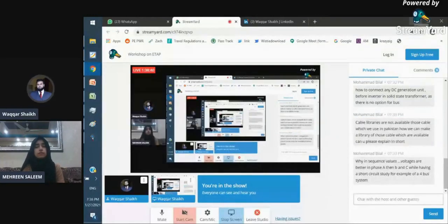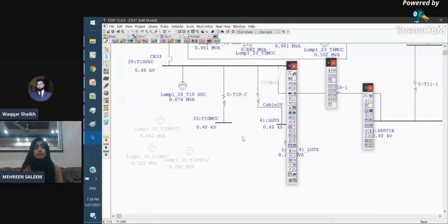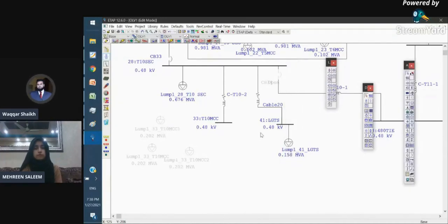Very good question, because ETAP's default library has some international vendors' database, and Pakistani cables, FR cables, or any local vendor cables are mostly not available in the ETAP software. So the first thing is, before modeling the cable, you must know the most important cable parameters which are to be taken from the cable manufacturer's database.